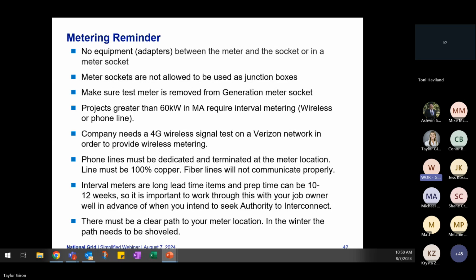For metering, no equipment adapters, as JJ discussed, between the meter and the meter socket. Sockets are not allowed to be used as junction boxes. Make sure the test meter is, that's a big one, make sure the test meter is removed prior to our personnel showing, so provide a picture that shows it has been removed. If a job is larger than 60 kW in Mass, it does require wireless metering. If that is the case, this needs to be on a 4G wireless Verizon network. If it is hardwired, there's no way to do wireless because of the location. It has to be 100% copper.